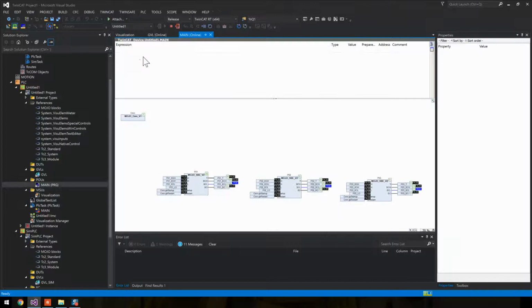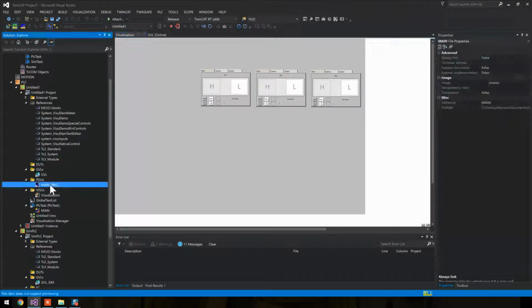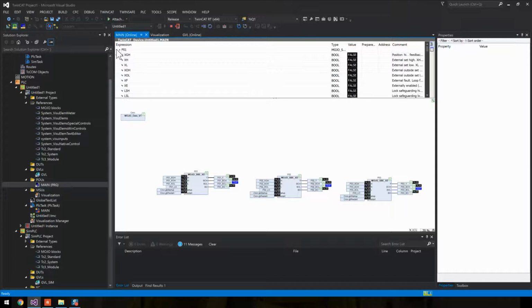It's probably hard to guess, but they do need to be enabled, and the default enable value is false. So we don't have an enable value, I mentioned this earlier, like binary feedback from the relay to the power supply to the pumps or something like that. But even though it's not available, we do need to initialize it.